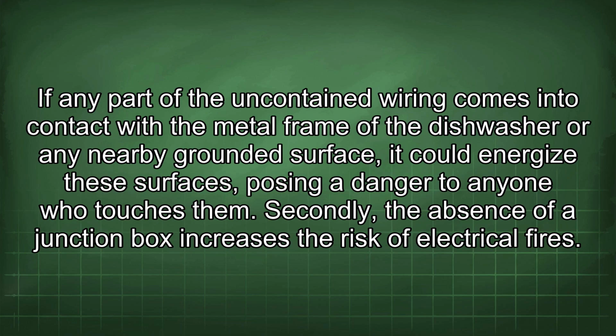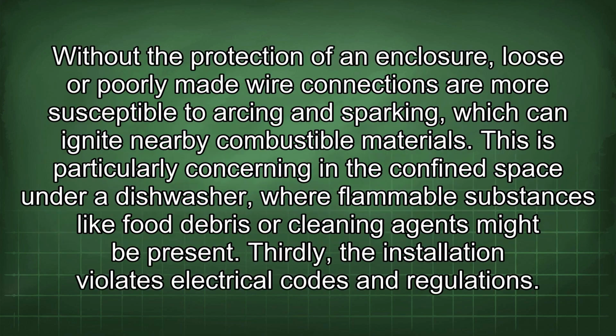Secondly, the absence of a junction box increases the risk of electrical fires. Without the protection of an enclosure, loose or poorly made wire connections are more susceptible to arcing and sparking, which can ignite nearby combustible materials. This is particularly concerning in the confined space under a dishwasher, where flammable substances like food debris or cleaning agents might be present. Thirdly, the installation violates electrical codes and regulations.